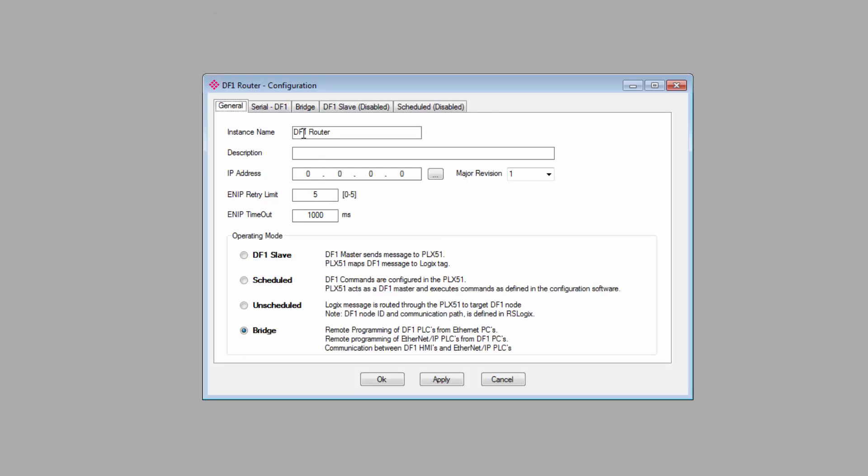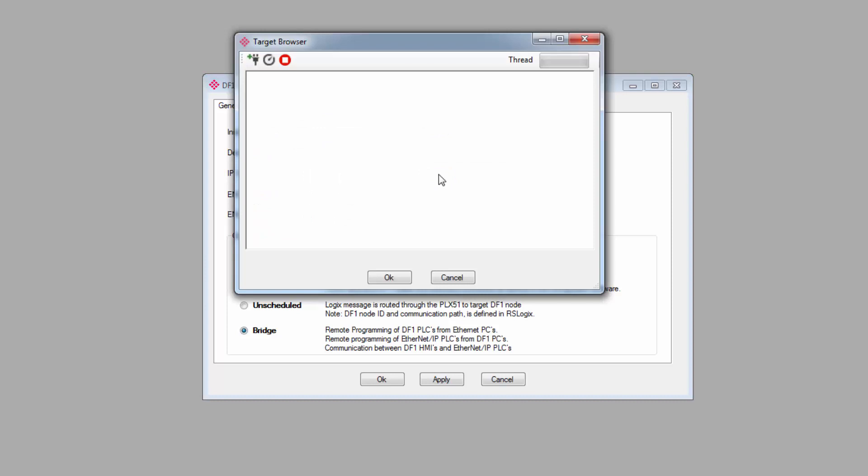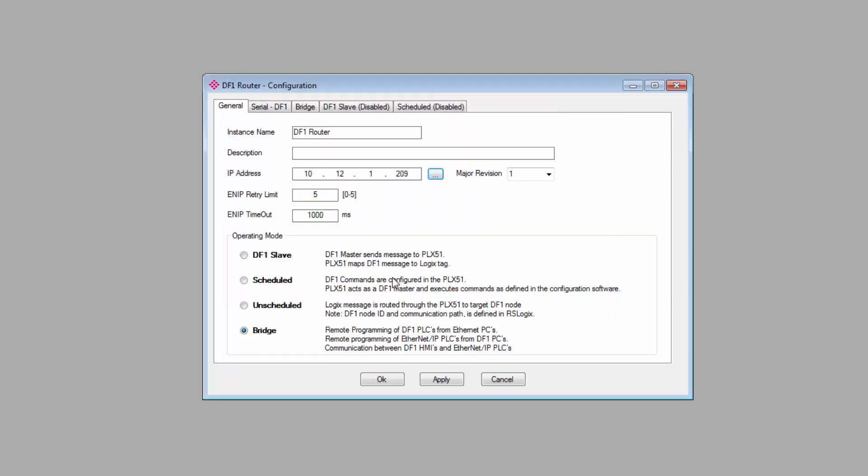You can see that we have five tabs at the top. The General and Serial DF1 tabs encompass the basic configuration for the gateway, and the other tabs will only be enabled depending on what mode you select. On the General tab, you can give the gateway an instance name and a description if you like. You then enter the IP address. Click the Browse button to the right of the address field to bring up the Target Browser, where you can see all the PLX51 gateways on your network. Select your DF1 module. It will have the IP address that you just assigned. Click OK, and the IP will appear in the address field.